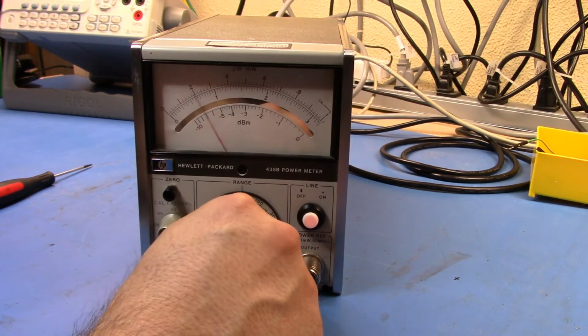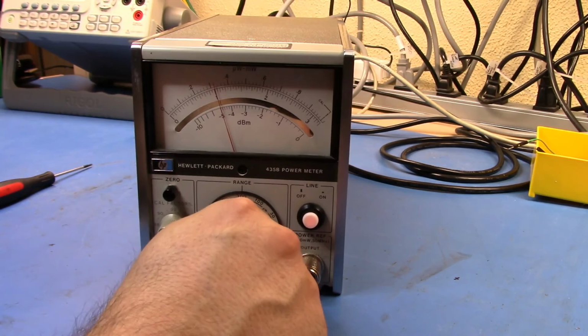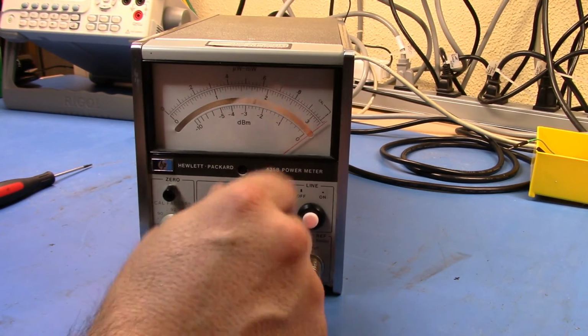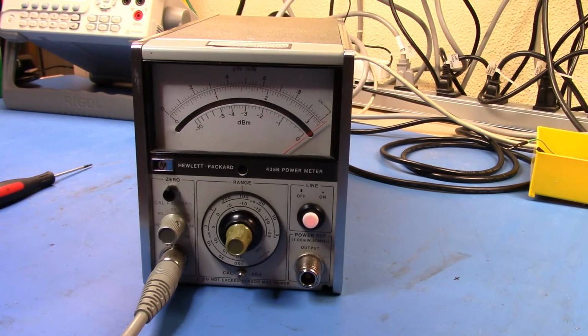If I went down to minus 5, you'll see the range come across, and then I can go down further. Now I'm at minus 13 dB roughly. So the 8657 isn't 100% accurate in terms of its output level, and I haven't done a range calibration on it, but overall it looks like it works out pretty well.